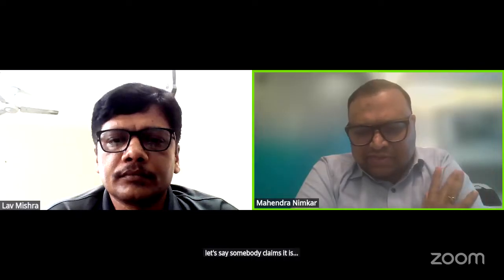No, see, XRF cannot check carbon. Any XRF instrument cannot check carbon, even if somebody claims it can at a high percentage, which nobody wants to check at that percent. So we generally say XRF is blind for carbon, because XRF measurements generally start from atomic number 12, that is magnesium, or 11, sodium, if it is a benchtop with vacuum. Carbon's atomic number is 6, so it is not possible with the X-ray fluorescence technique.